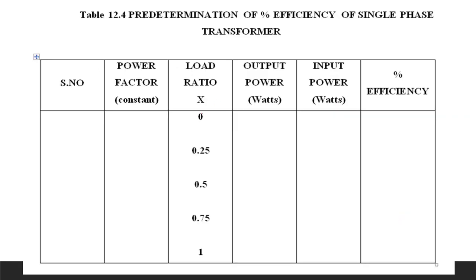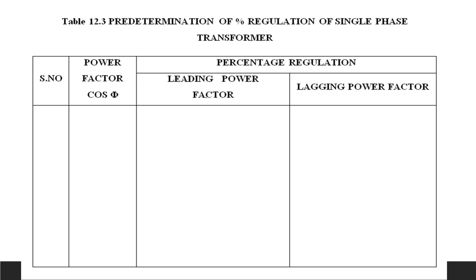To find the efficiency, fix the load ratio x at values 0, 0.25, 0.5, 0.75, and 1. The power factor can be kept constant at 0.8 for all readings. Calculate the output power, input power, and efficiency for each corresponding load ratio and power factor. This is the predetermined methodology for calculating the efficiency of a single-phase transformer.